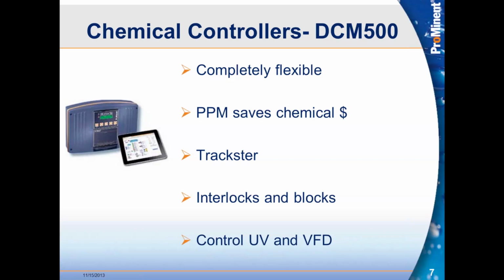And again, back to the smart disinfection, we're doing these things only when we need to and in an amount that's needed. We can also take information to a VFD. We can take the flow meter signal that we've taken in for display, for remote display, for interlocking, and we can also send that signal over to a VFD, and then the VFD can modulate off the gallon per minute set point that is programmed into it.